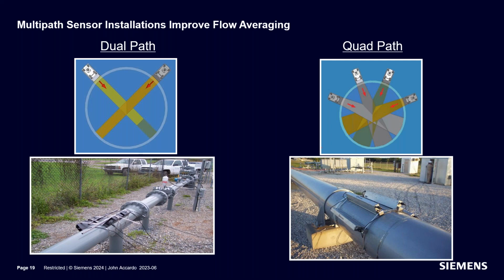So it's going in one beam and then out in one beam and into the other beam and so on. And so a properly operating multiple beam system, you'll see the paths mirroring each other. When one path goes up in reading, the other path goes down in reading, and vice versa. And so the average stays constant.